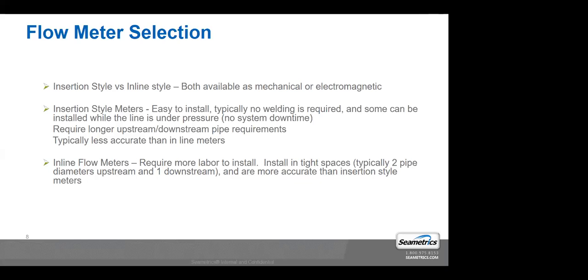The main reason they're less accurate than inline meters is because the manufacturer of an insertion meter, they don't own the pipe diameter that meter's being installed in. They don't calibrate the meter to that known diameter. So if there's sediment buildup in that pipe, there's all types of variables. How far is that meter being inserted in the pipe? Is it only measuring one point across? Is it multi-point? There's all types of variables with insertion meters. So as a rule, they're not as accurate as full bore inline meters.